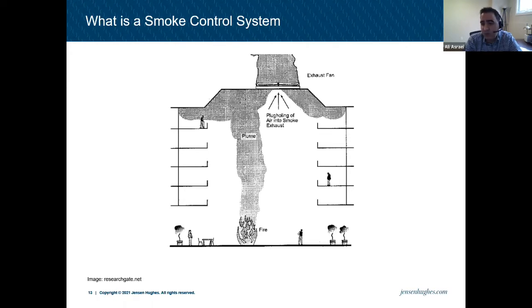So as you can see in this image here, see the fire is going up. Basically, they're managing the smoke, right? So smoke is going through this atrium and out. So we try to prevent the smoke getting into the floor areas by adding air curtains here and here, like supply fans, pushing the smoke back into this atrium and providing this path for it to get out of the building. So that's another thing that we can consider as a smoke control system.